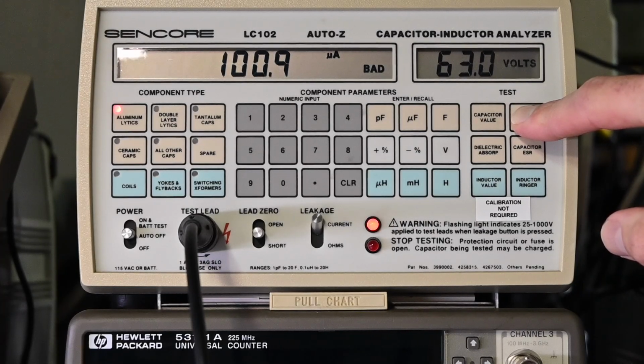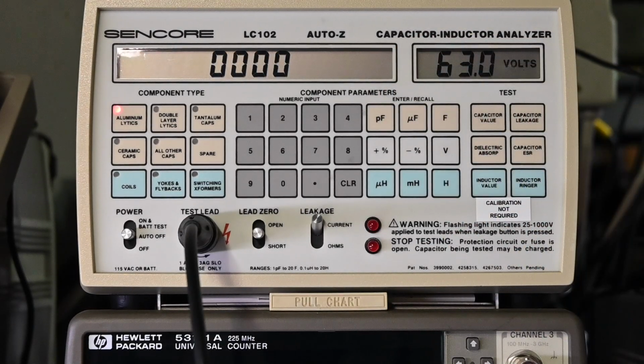So that value is remaining much too high. It initially starts as a higher current because the capacitor has to charge, but it should basically fall near zero. Electrolytics always have some leakage current, but this is excessively high. So, it's remaining way too much current through that capacitor. Even though it's in microamps, it's still too much. And you can see that, it does say bad on the display.